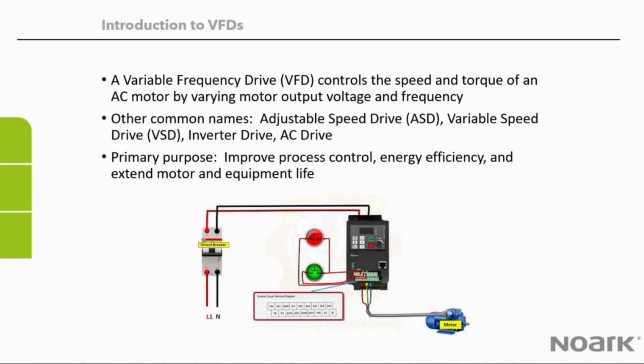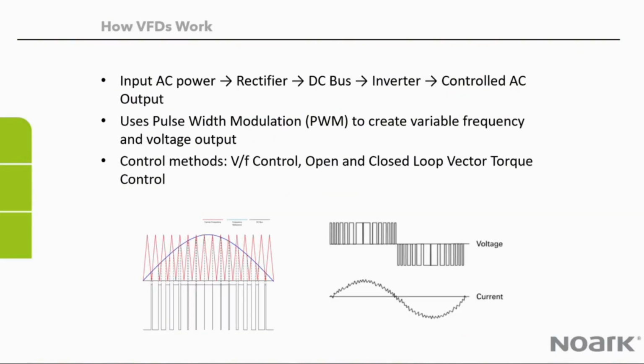You get a lot of energy efficiency from using a VFD, and you also extend the motor and the equipment life. If you are using older technologies, you may go like a starter from 0 to full speed in a heartbeat, and that's hard on the motor, hard on the mechanical, and also hard on the utility. So a VFD solves a lot of those problems.